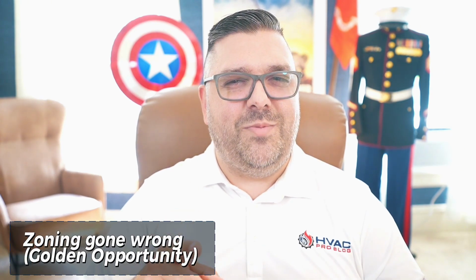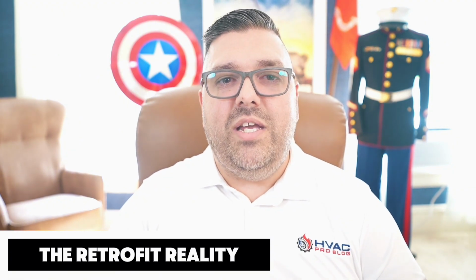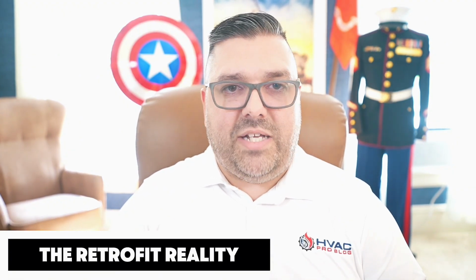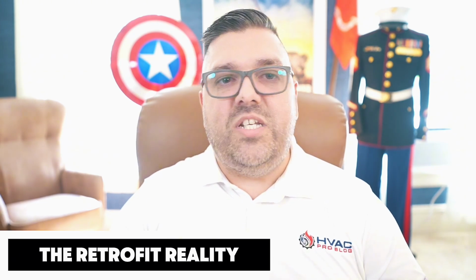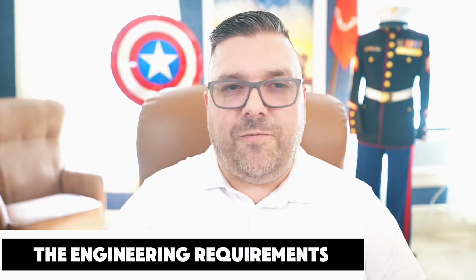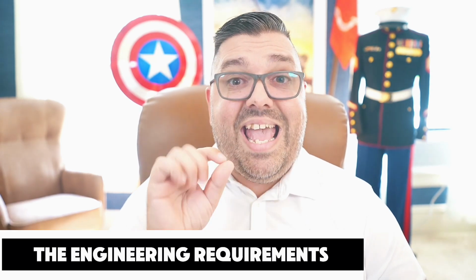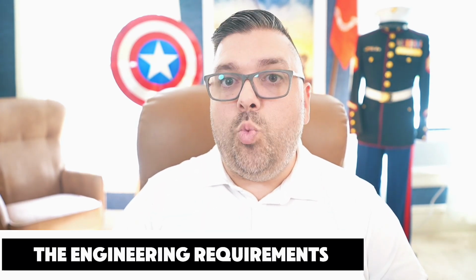Let's talk about a zoning system gone wrong. That's probably the golden opportunity. Everyone wants zoning these days. But here's the brutal truth. Most systems aren't designed for it from the ground up. Let me show you how to turn this challenge into the golden opportunity. Adding zoning to an existing system is like trying to convert a highway into a neighborhood street system. You need proper bypass dampers, static pressure controls, and often complete duct modifications. If you skip these fundamentals, then you're creating more problems than you're solving. Proper zoning requires understanding minimum airflow requirements, bypass calculations, and static pressure management. When zone dampers close, where does that air go? Most retrofit installations ignore this critical question.